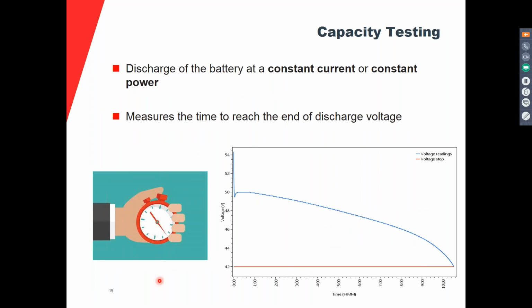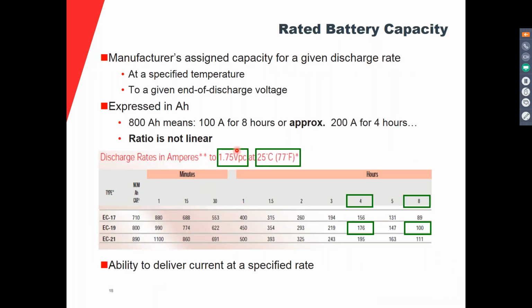So the capacity testing that we have been mentioning a lot is actually discharging the battery at a constant current, using that current from the manufacturer's table, or at a constant power. The tables are also provided in terms of watts instead of amps. But the idea is that if you're running the test to determine the capacity value of the battery, it has to be performed at a constant current or constant power. And you need to measure the time that the voltage takes to reach the end of discharge voltage that we mentioned previously. So these 1.75 volts per cell times the amount of cells.